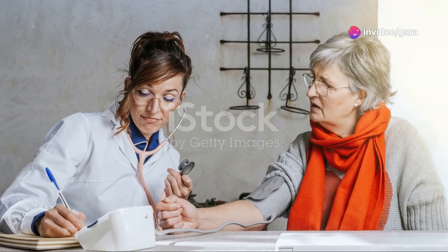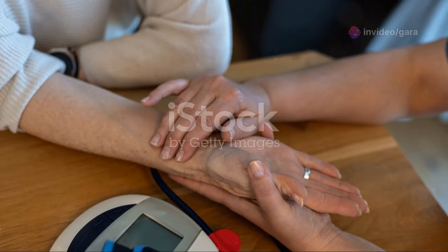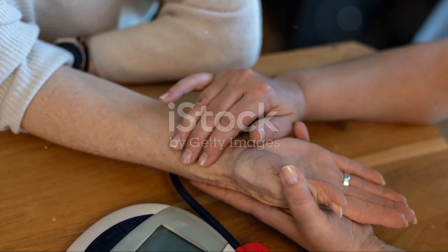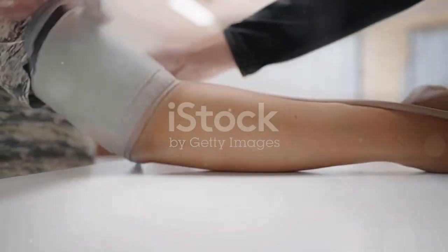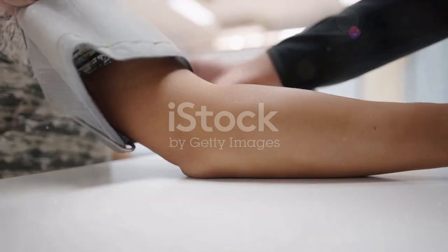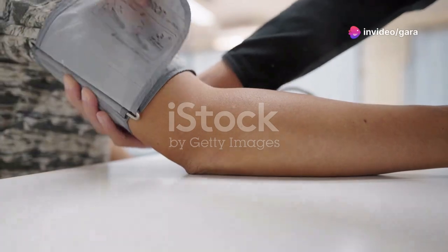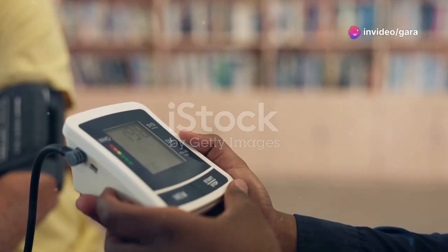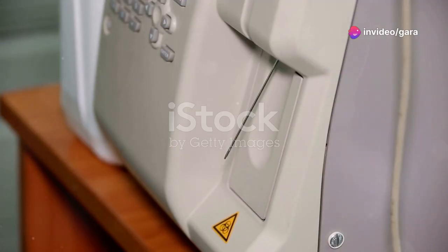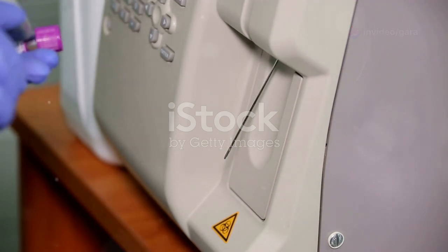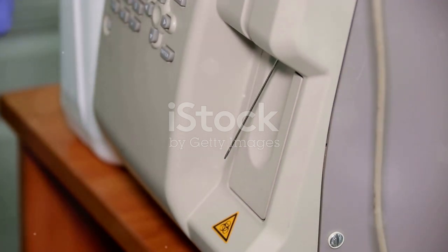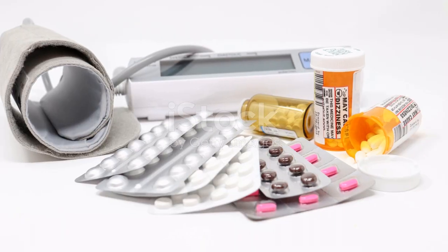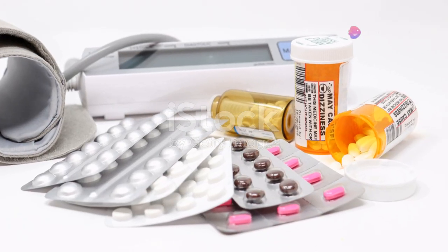The systolic pressure is the point at which the oscillations start, representing the pressure when your heart beats. The diastolic pressure is when the oscillations end, representing the pressure when your heart is at rest. To sum it up, the pump inflates the cuff. The pressure sensor detects oscillations as the cuff deflates, and the algorithm calculates the blood pressure from these oscillations. It's a brilliant interplay of mechanics and math.